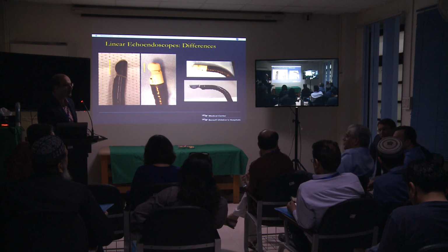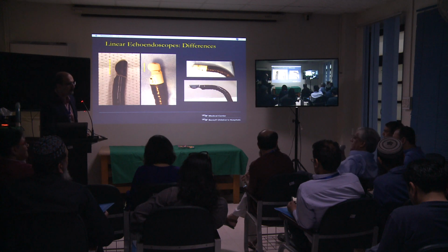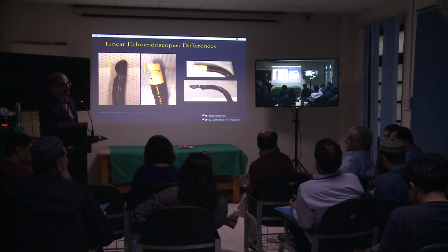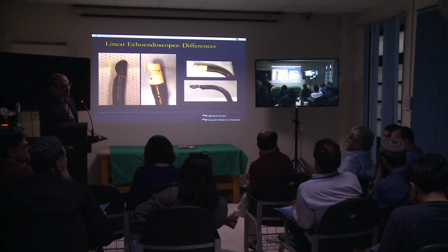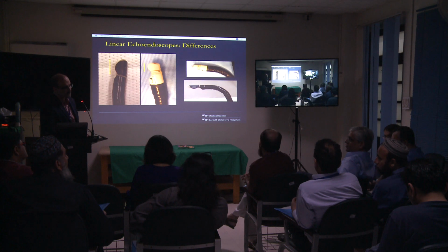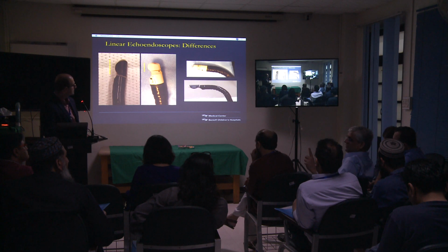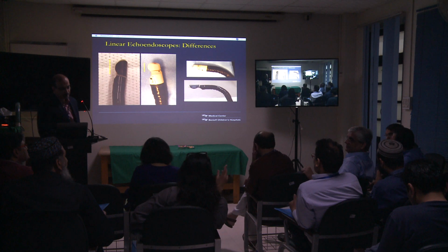Yeah, absolutely. One other point, if I may add, with the repair: whichever company you go for, with an EUS scope, once it breaks, they have to send it away. They cannot repair it here. That is another reason why I feel you need to be very careful using it. If you have one scope, I think it should be used very, very carefully because when it goes for repair, it can be gone for 2 months.